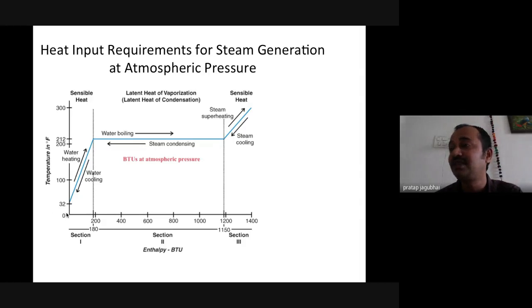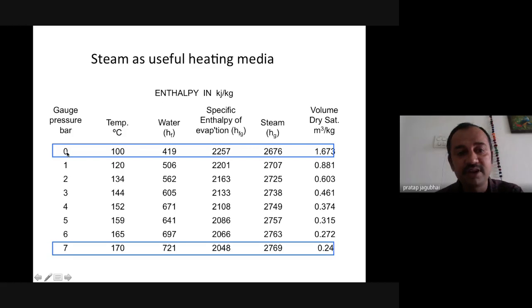So that is the advantage of steam being utilized in a wide way as a utility for the process industry. Now, this will give you a clearer picture: when the steam pressure rises from 0 bar gauge to 7 bar gauge, the feed water at 100 degrees becomes steam, and at 170 degrees centigrade steam is available. The enthalpy of steam goes from 640 kilocalories to 662 kilocalories. Now this is more important: at 0 bar gauge the volume was 1.67, and it has been reduced, which means the steam becomes denser.